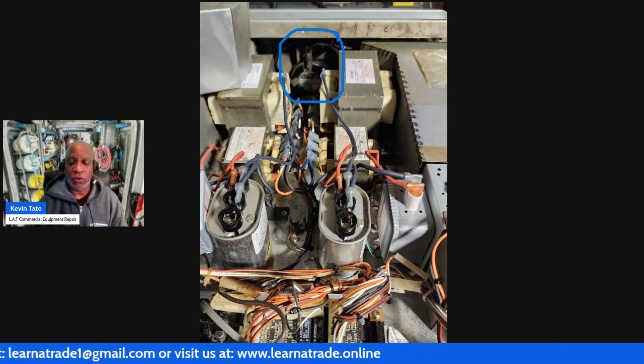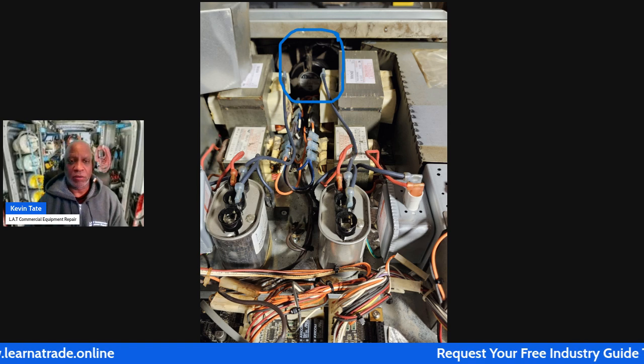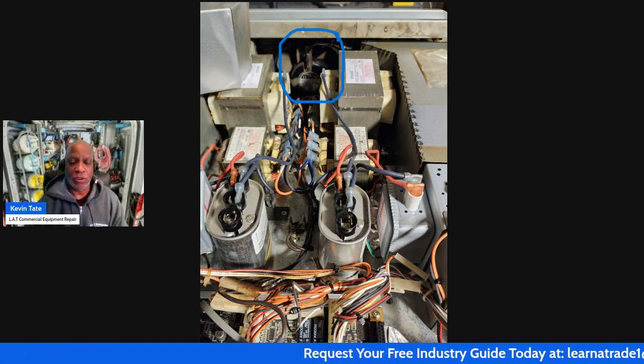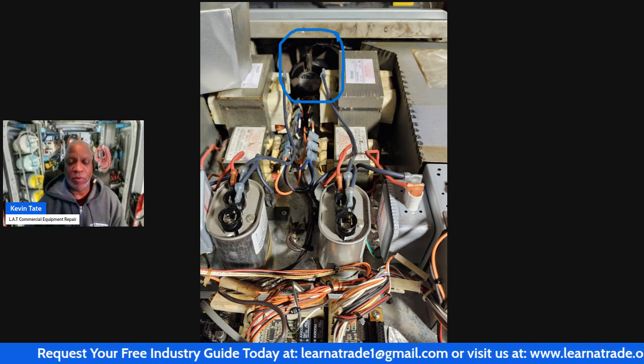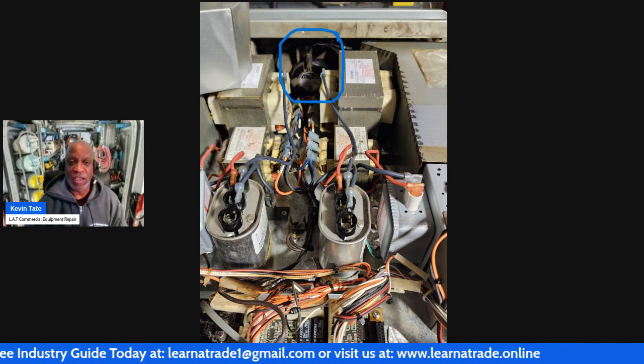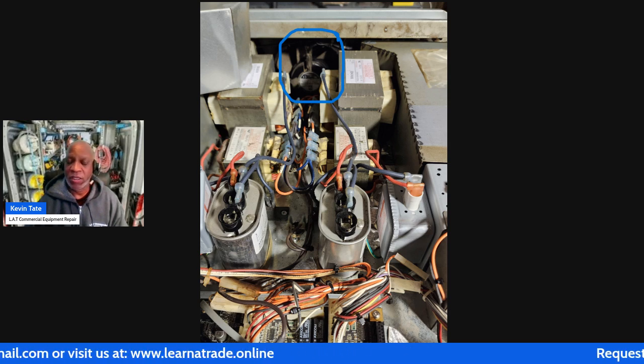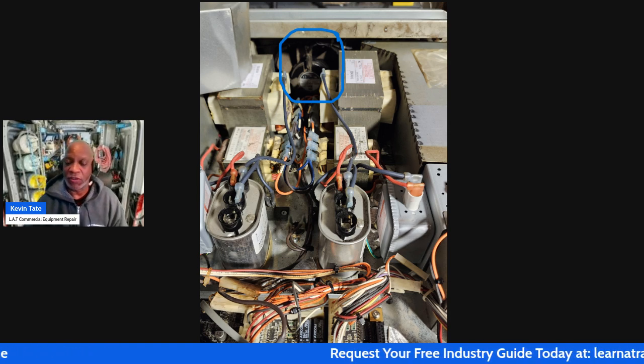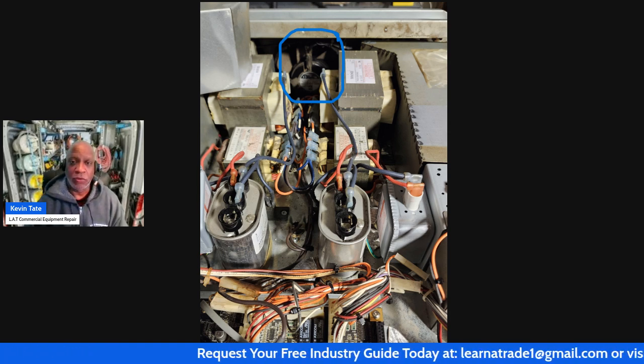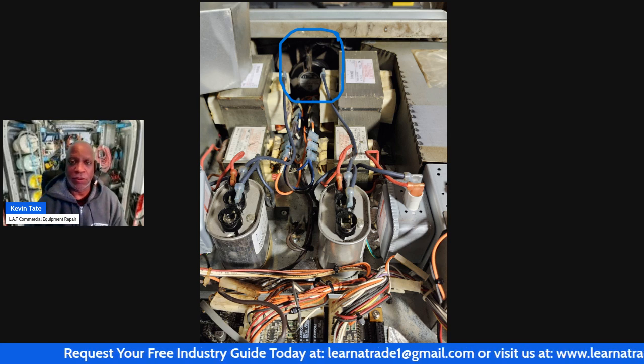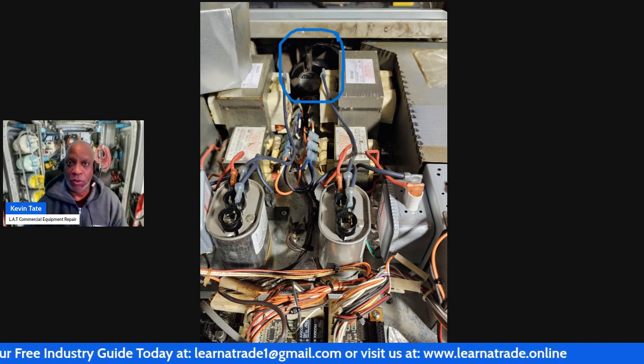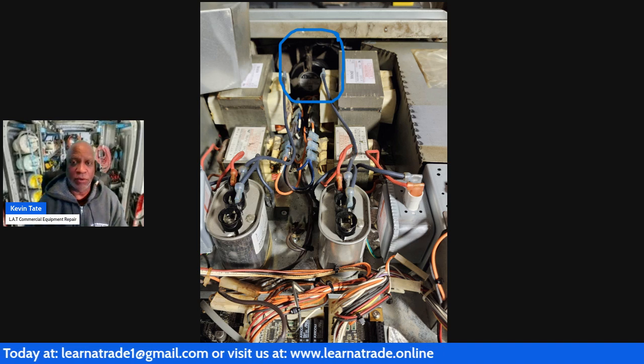That's the fan that cools that electrical compartment. So the first measure I would look at is to pull that air filter from the back, and a lot of times you'll find that air filter matted with dust and grime. Some of them are very bad because the staff doesn't take time to clean them. So basically you're looking at a blockage of airflow when you have those EC temp errors.